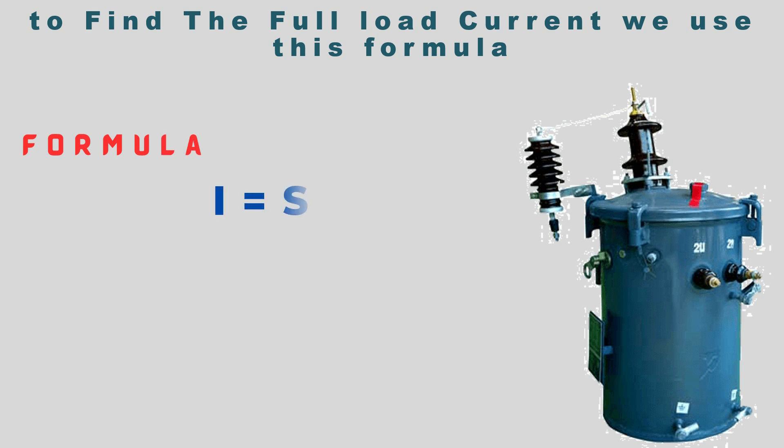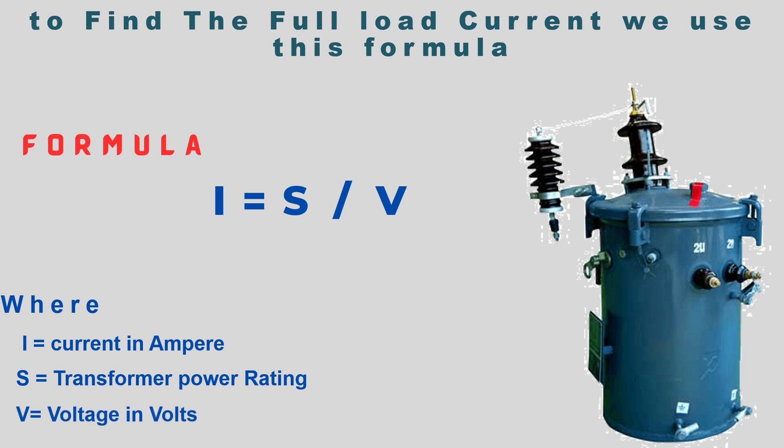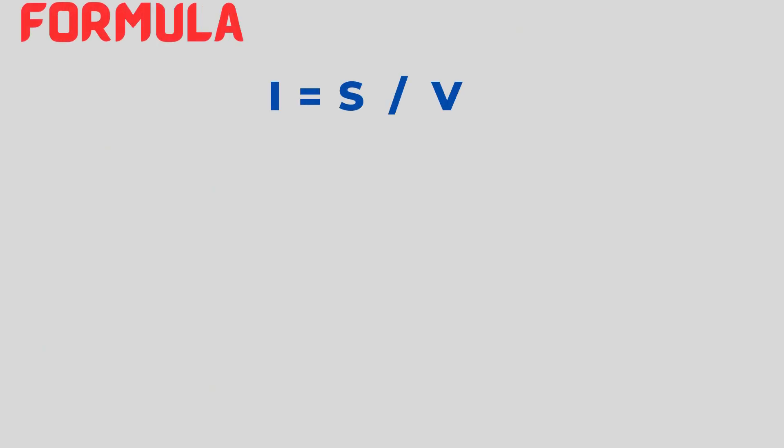I equals S divided by V, where I is current in amperes, S is transformer power rating in VA or kVA, and V is voltage in volts. Using this formula, we can calculate the current for both the primary and secondary windings.